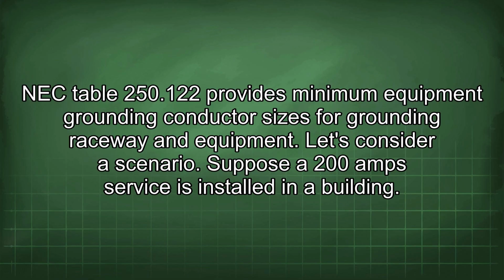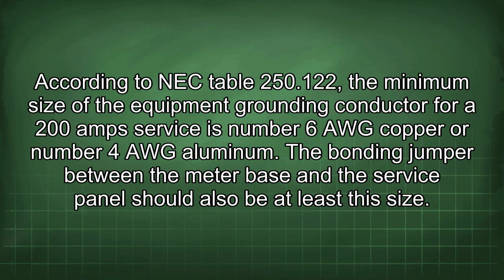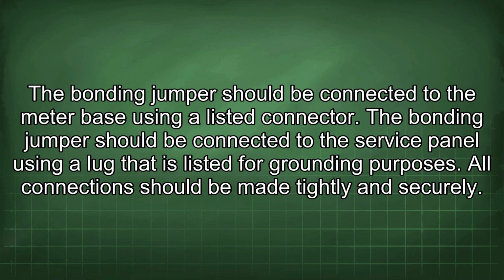Let's consider a scenario. Suppose a 200 amp service is installed in a building. According to NEC table 250.122, the minimum size of the equipment grounding conductor for a 200 amp service is number 6 AWG copper or number 4 AWG aluminum. The bonding jumper between the meter base and the service panel should also be at least this size. The bonding jumper should be connected to the meter base using a listed connector. The bonding jumper should be connected to the service panel using a lug that is listed for grounding purposes. All connections should be made tightly and securely.